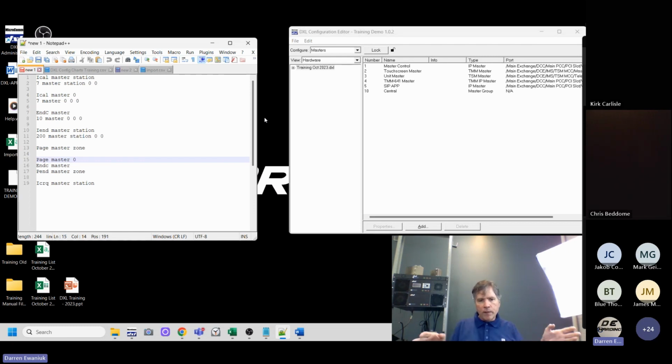So if you write a block of 5 registers, in most cases, even though your programming will write them one at a time, your driver software will condense them. You've made 5 little changes, but it'll wait a little bit and only send the changes once it knows you're not making any more changes. So in most cases, it will send that as one block in one network message. If that's the case, it's not a problem. You're sending the whole command at once.